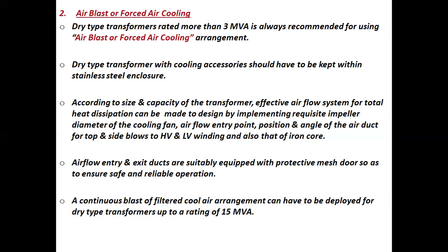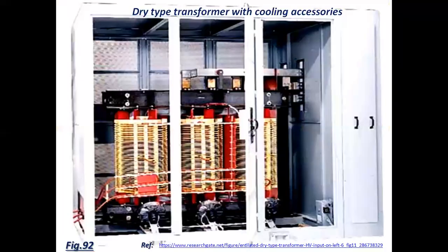Airflow entry and exit ducts are suitably equipped with protective mesh door so as to ensure safe and reliable operation. A continuous blast of filtered cool air arrangement can be deployed for dry type transformers up to a rating of 15 MVA. See the diagram, dry type transformer enclosures. Dry type transformer with cooling accessories.